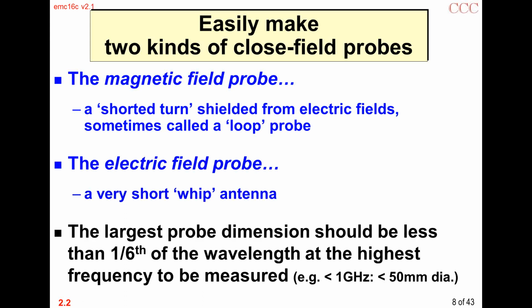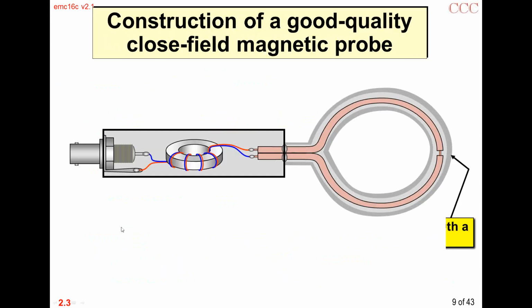The key thing is the largest probe dimension - the length of the whip or the diameter of the loop - should be less than 1/6 of the wavelength at the highest frequency you want to measure. So for a gigahertz in air, we're looking at less than 50 millimeters in diameter. If you don't do that, they start to get a bit resonant and you can get complex behavior from them, so it's best to use them a long way short of their first resonant frequency.